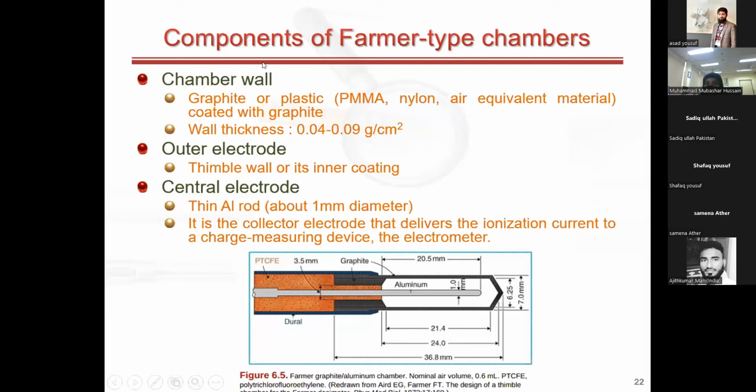So components of any Farmer type chamber include the chamber wall. In the actual Farmer chamber, this wall was made of graphite. But now, in many commercially available Farmer type chambers, it could be made of some plastic or polymer, including PMMA, nylon, or some air equivalent material. All these materials are almost air equivalent. They have effective Z slightly lower than that of air.